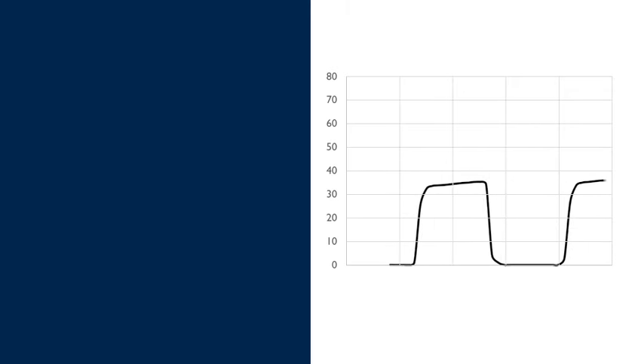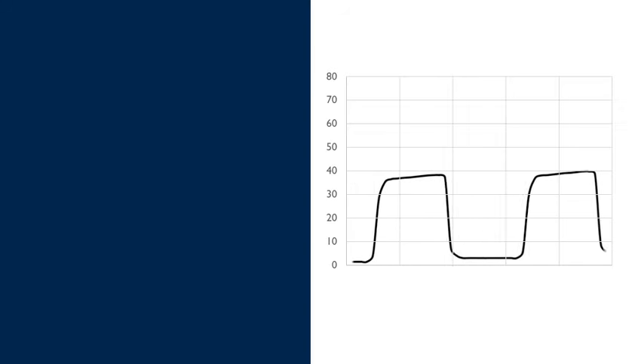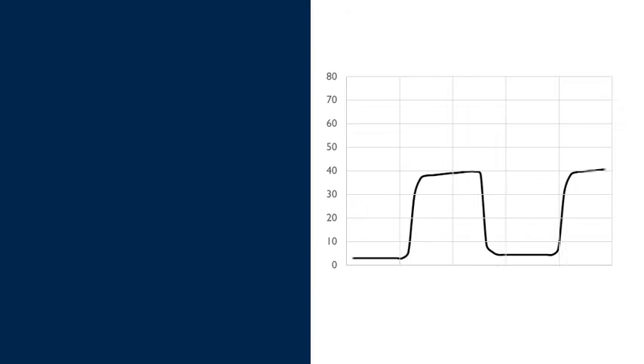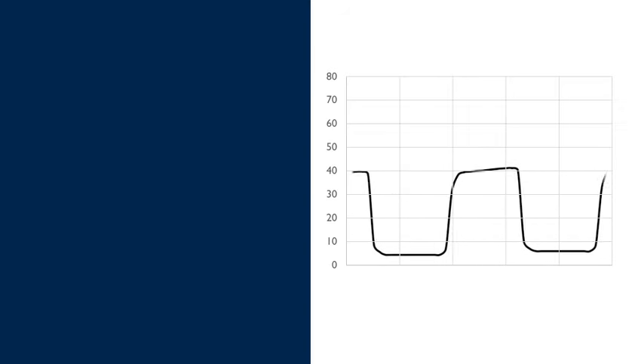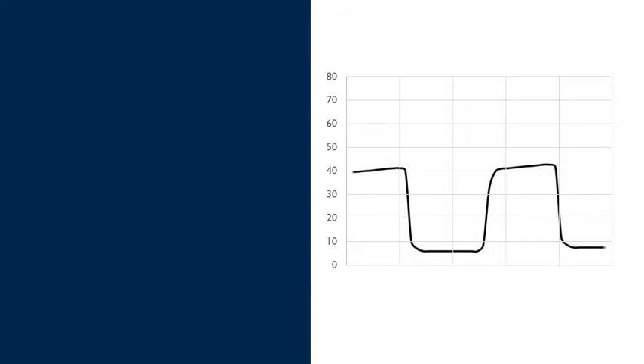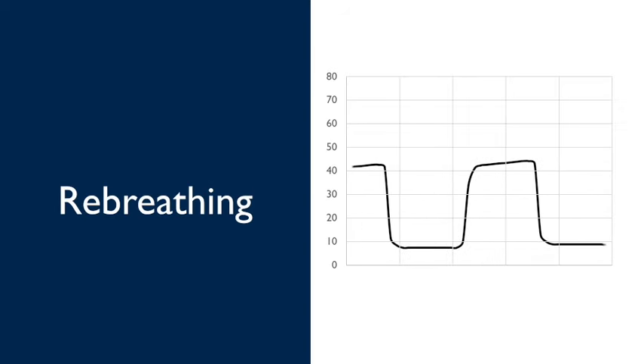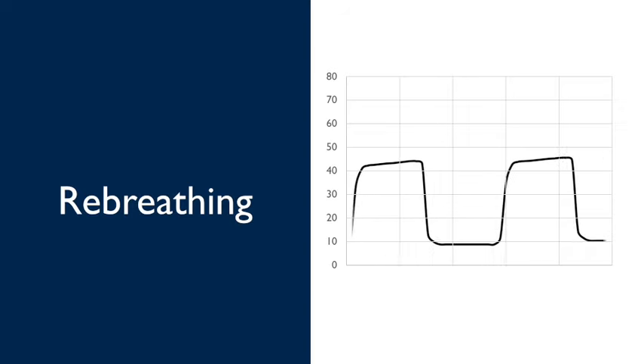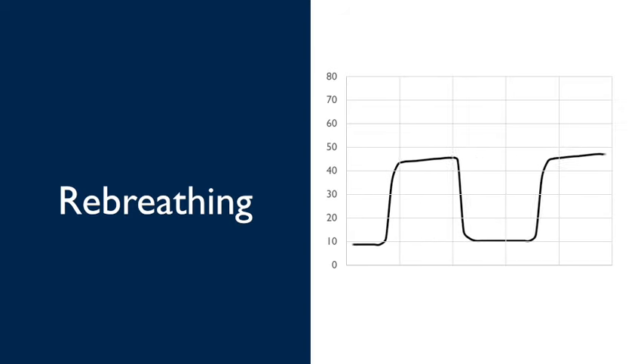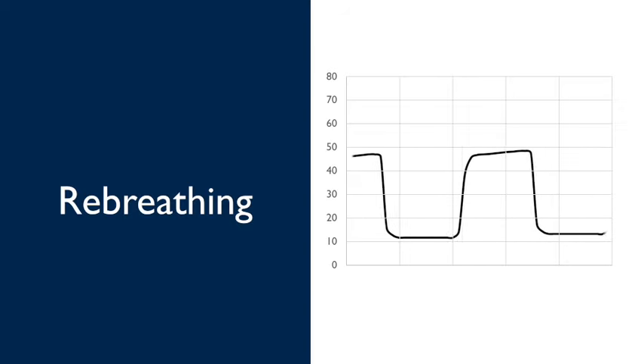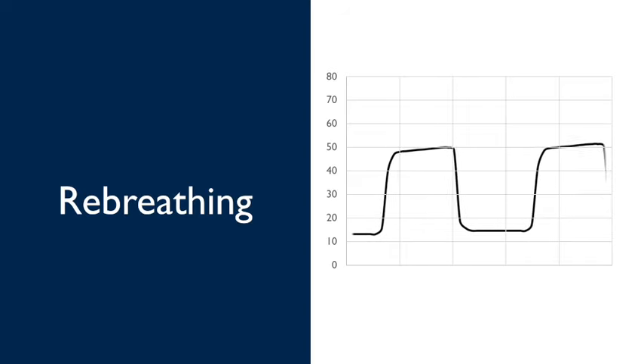Our next example starts off looking just like the previous one, a gradually increasing end-tidal CO2. But here's the difference. The end-tidal isn't returning back down to zero during inspiration. Why? It's because the patient is re-breathing. The patient has too much mechanical dead space, or the expiratory valve is not working, causing the patient to re-breathe all their previously exhaled CO2. The point being, if you see a waveform that looks like this, there may be something wrong with the ventilatory circuit itself.